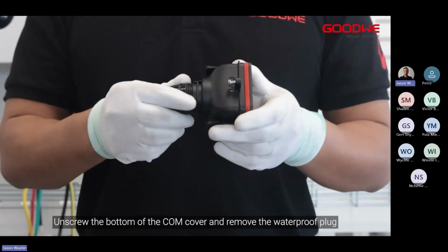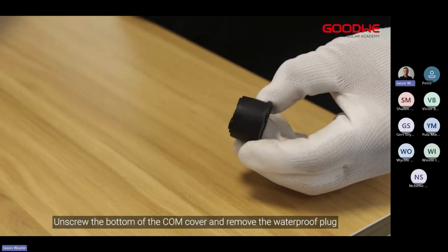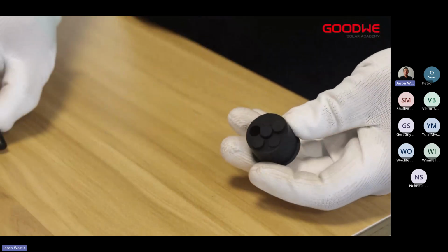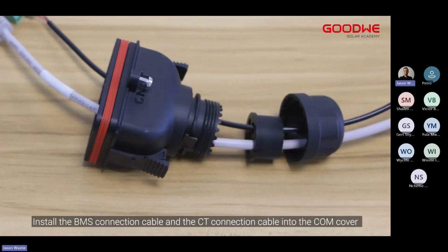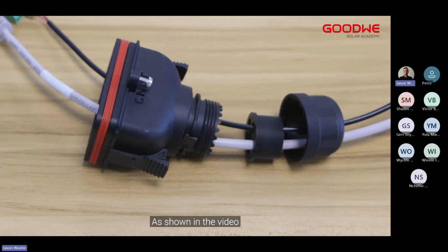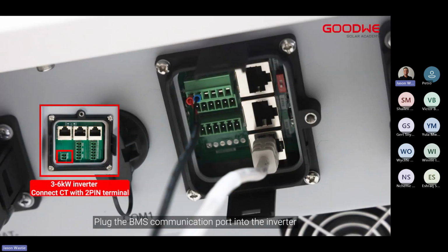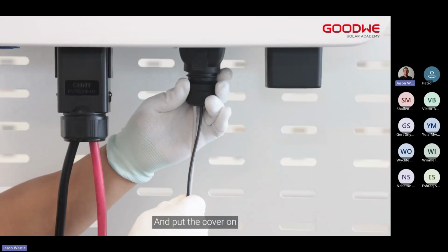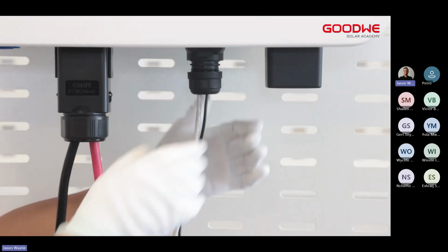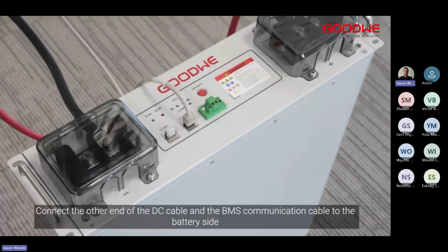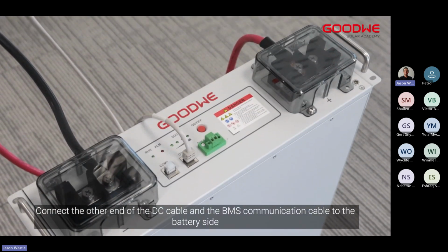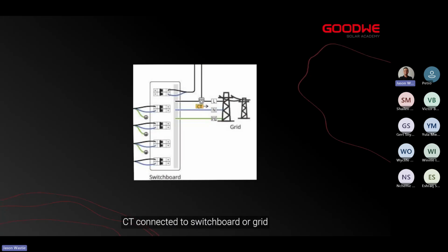Unscrew the bottom of the COM cover and remove the waterproof plug. Install the BMS connection cable and the CT connection cable into the COM cover as shown in the video. Plug the BMS communication port into the inverter. Plug the communication terminal into the corresponding port. And put the cover on. Connect the other end of the DC cable and the BMS communication cable to the battery side. CT connected to switchboard or grid.